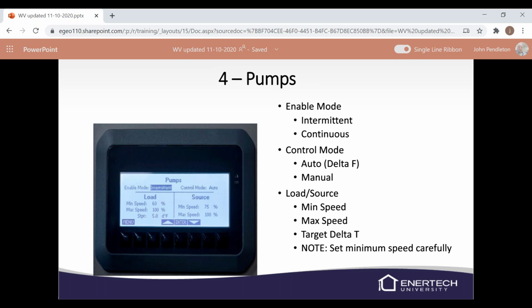If you ever run your load and source pumps and you see that the flow, which is reported in GPM, bounces around a lot, let's say from 9 GPM down to 2, back up to 8, over to 6, I can tell you that means you've got air in your system. You may say, well, I just flushed it. Sometimes those micro bubbles don't want to come out. Again, that's why we've incorporated the hydraulic separator and the buffer tank to kind of eliminate those issues. So if you do see it bouncing around, know that it's almost positive to be air in the system.